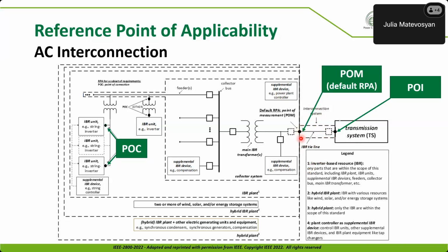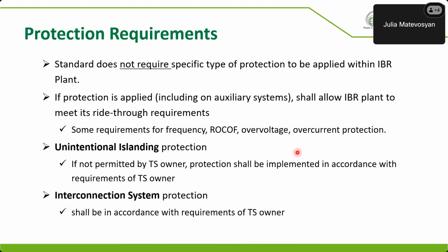Obviously, you have heard this before many times. Most all requirements of the standard apply at the point of measurement, that is the high side terminals of the main power transformer. And protection requirements, we did not really spell it out. Wherever the protection is applied in the plant, they need to follow the standard and make sure that those protections do not interfere with the ride-through capability of the standard. All right, with that said, as I said, the standard does not require a specific type of protection. I think the reason we ended up writing this statement very clearly and repeated it quite a few times is because if you look at IEEE 1547, then I think it requires DER to trip for certain voltage deviations of given duration or frequency deviations of given duration. But we want to make sure that these are IBRs that connect to transmission, sub-transmission system, and there is no requirement like 1547.